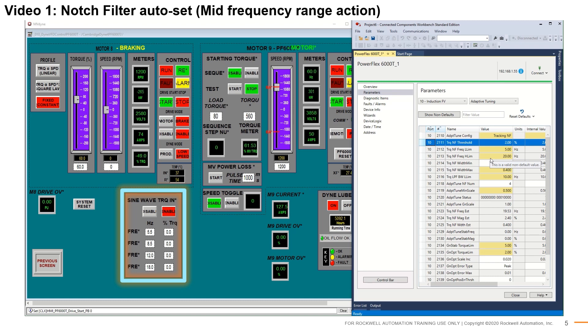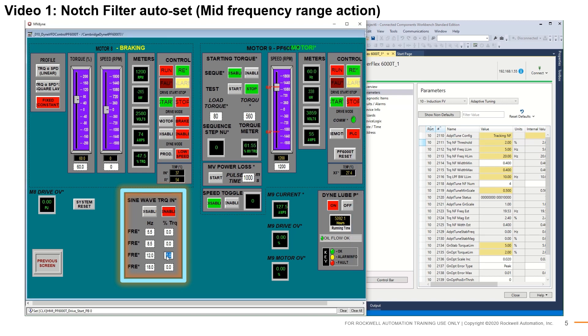Let's start injecting frequencies with the sine wave utility. For every injected frequency, observe that adaptive tuning identifies the frequency we just injected and the torque reference notch filter is set to match that frequency.